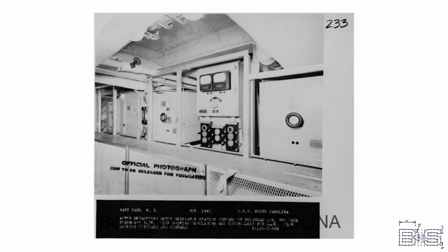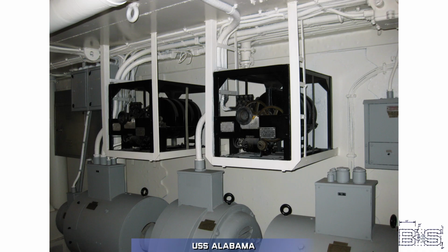The power for these coils comes from degaussing generators. These are basically motors connected to one or more generators. The idea is you want less volts and more amps to generate a larger magnetic field. For example, the North Carolina motor generator sets are capable of generating DC at 1,500 amps, but only 20 volts.